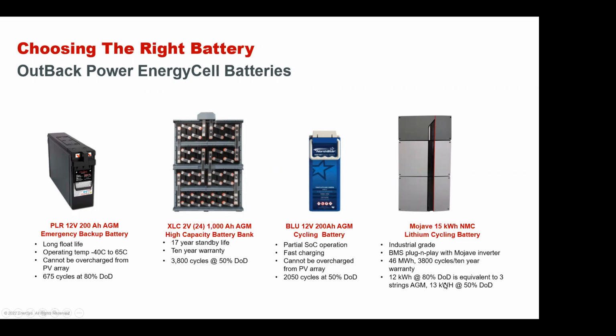But the other thing you have to keep in mind is that if you're in a cycling application, at most you're probably going to get 5 years of battery life out of it, and probably less. And you'll need to get another 3 strings. So you're really looking at 3 strings of battery over the 10-year life equivalent of Mojave. You'll also need a battery rack for it. So by the time you add up all those costs, they're pretty comparable to a Mojave battery.